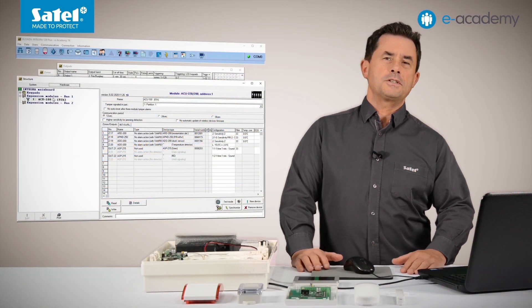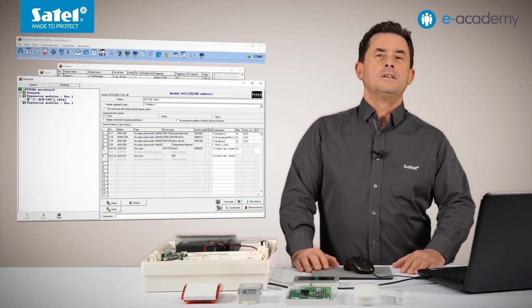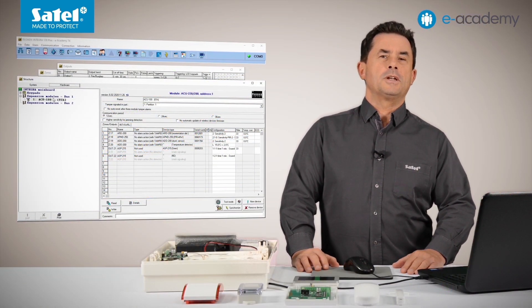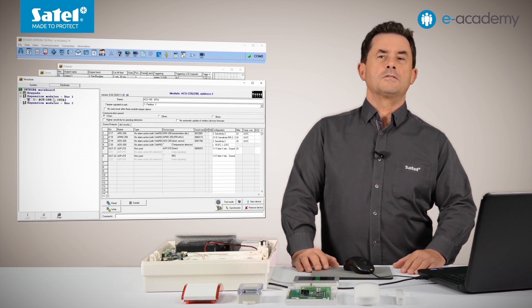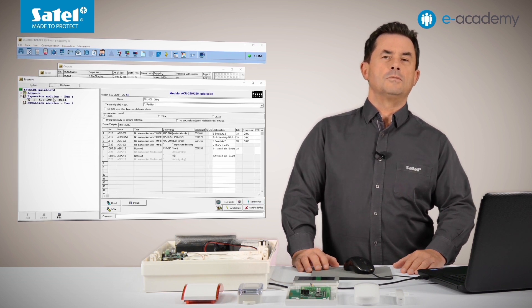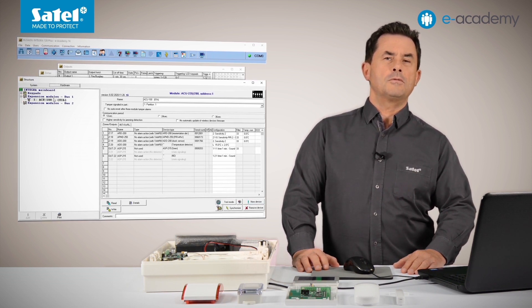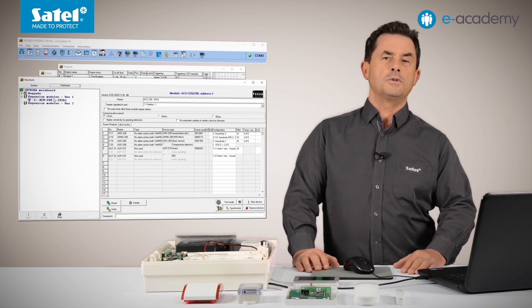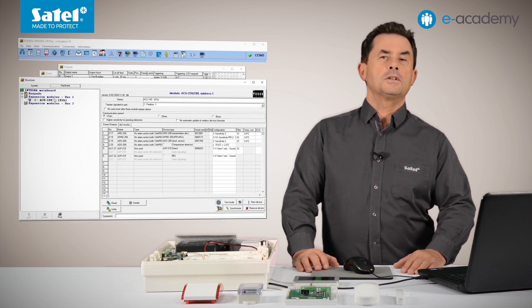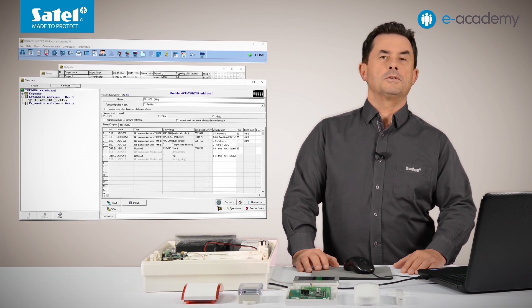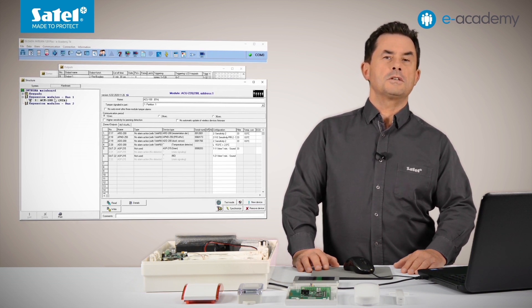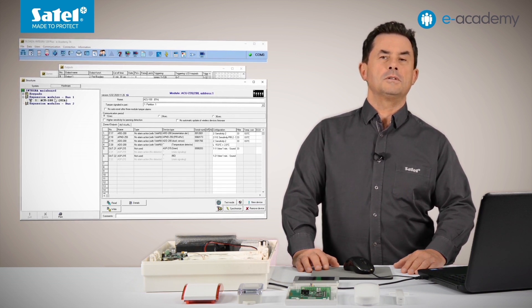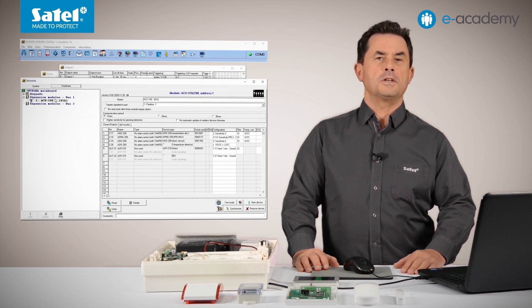Another important observation: information about the temperature is transmitted to the ABAX2 system controller at regular intervals during periodic communication. Therefore, when the temperature around the detector changes, this information may reach the controller with some delay.